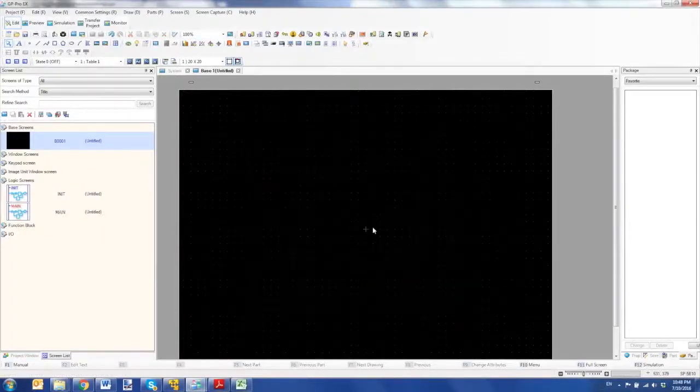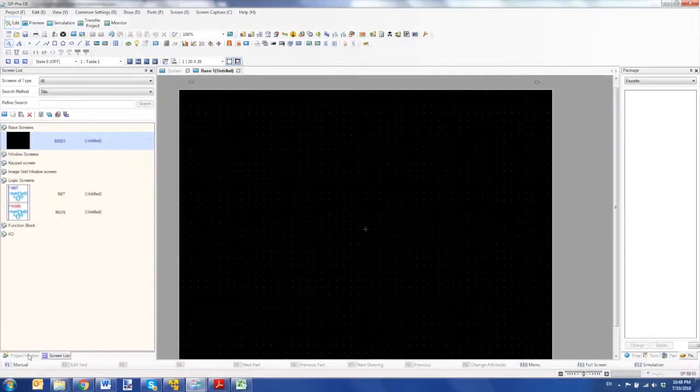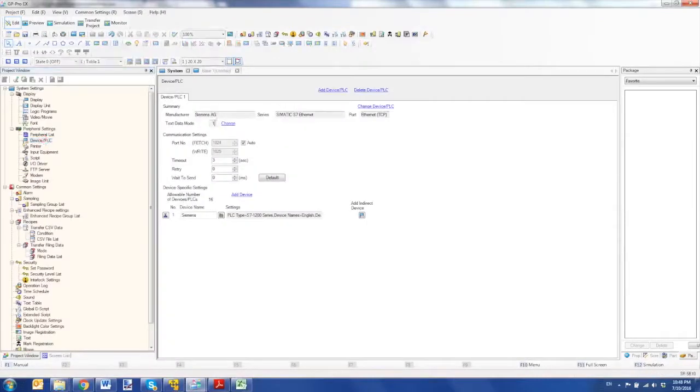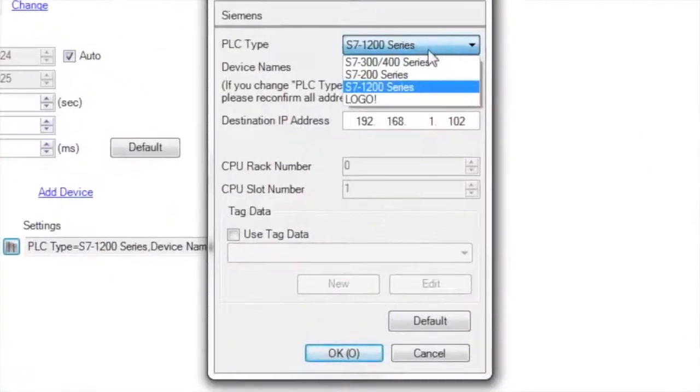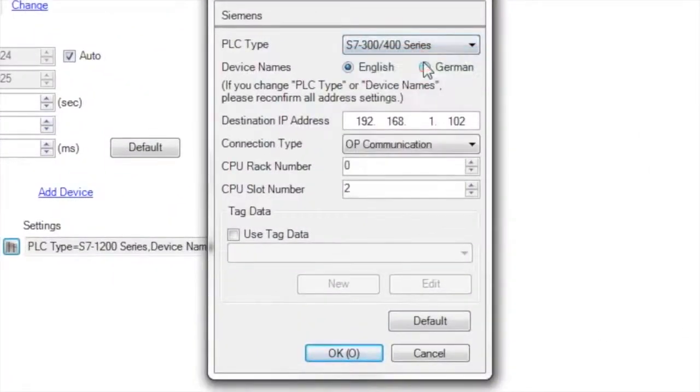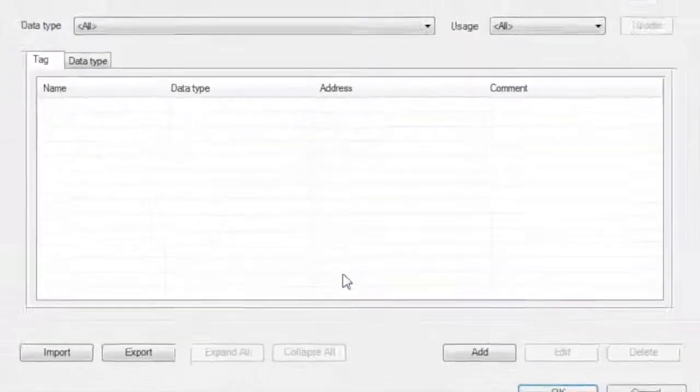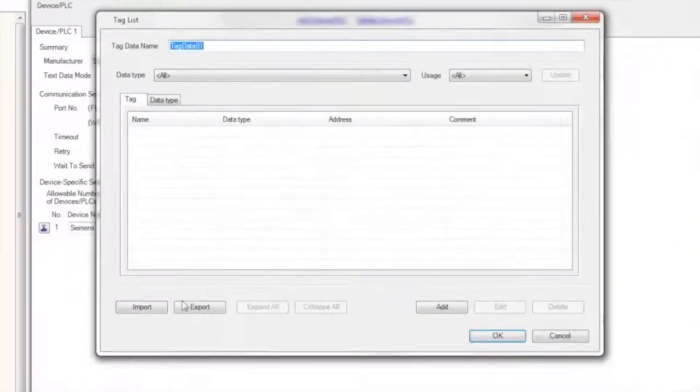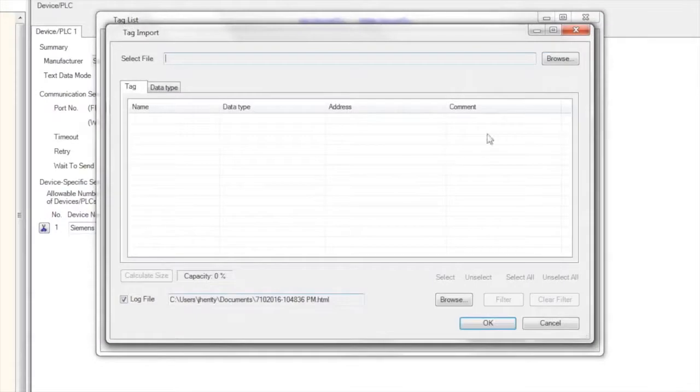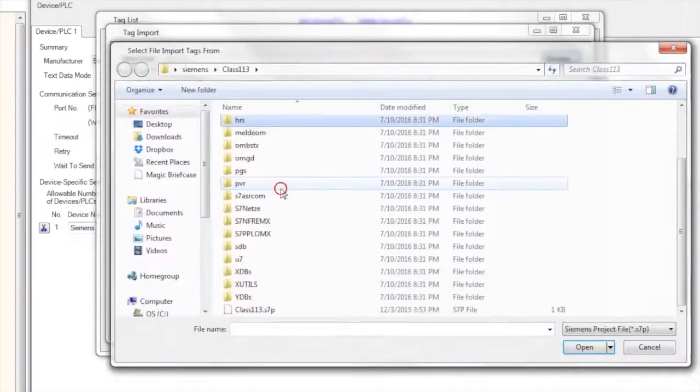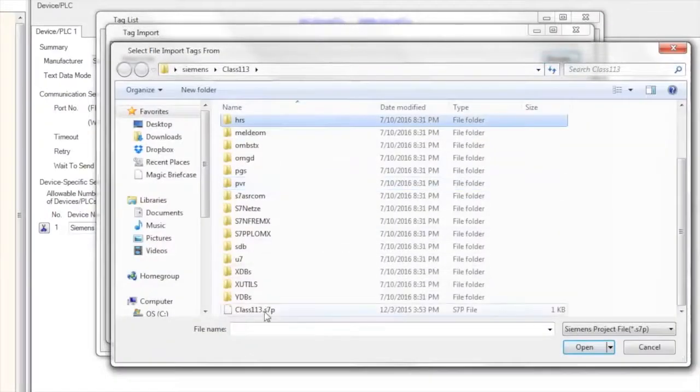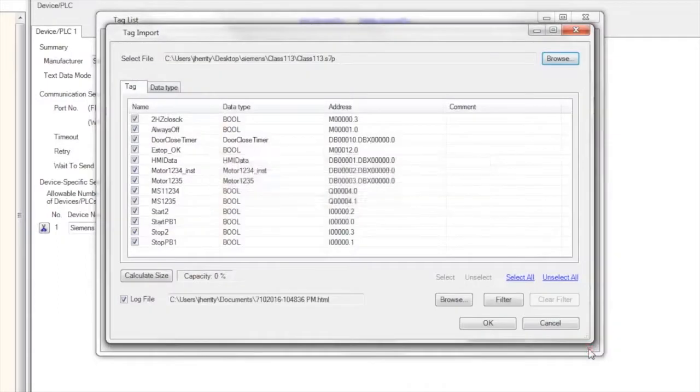So to give a quick demonstration of how that works, I will go back to the PLC window and select device PLC. What I'm going to do is change the series here to S7-300, 400 and we're going to use tag data. If I select new, I can then go to import, browse, select the S7-P file and all the tag data will come in.